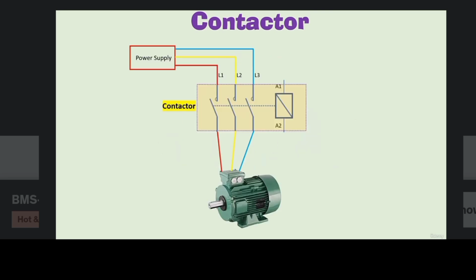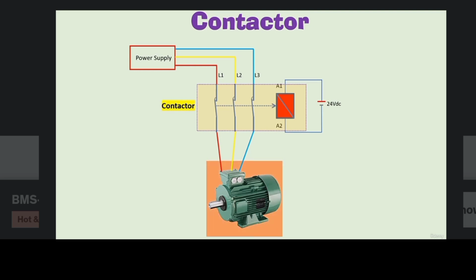Here is how to wire a contactor to control switching of an electric motor. Here, three-phase power supply is applied on one side of the contactor, while the other side is connected to the motor. This is the direct online starting method for the motor and is usually used for motors with ratings up to 7.5 kW. For larger motors, a star-delta starting circuit is used, which is explained in detail in an upcoming section. So when a control voltage is applied on the contactor coil, the magnetic field generated inside the contactor closes the contact points, and the power is now applied on the motor and the motor is turned on.